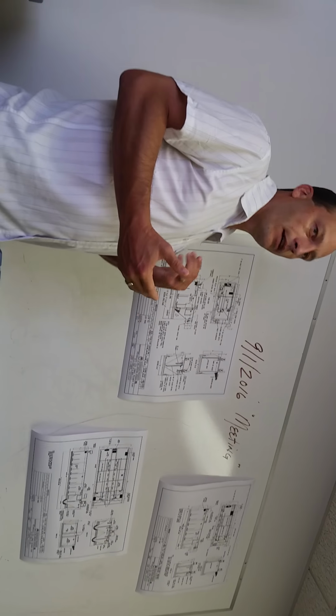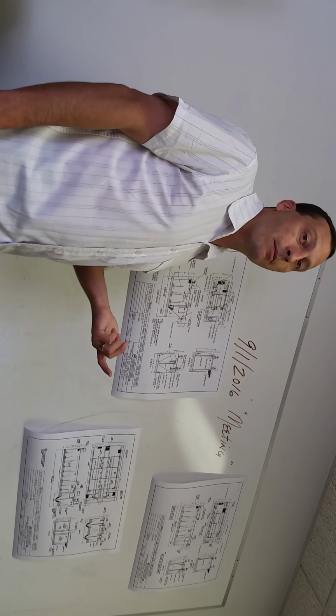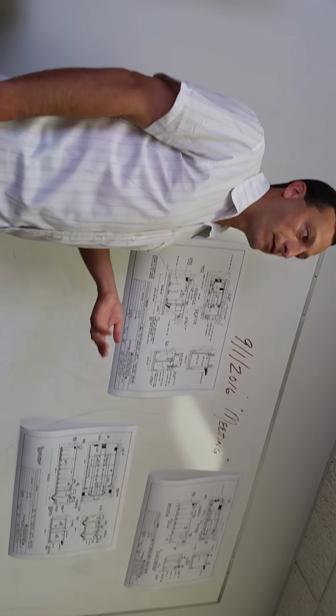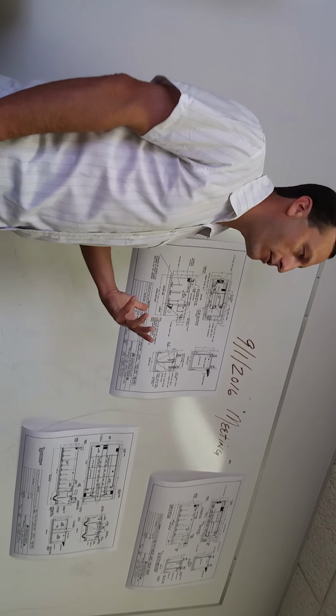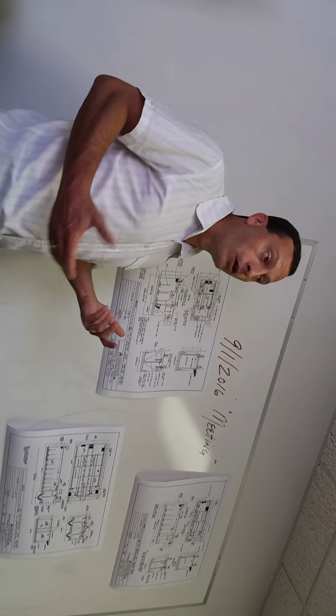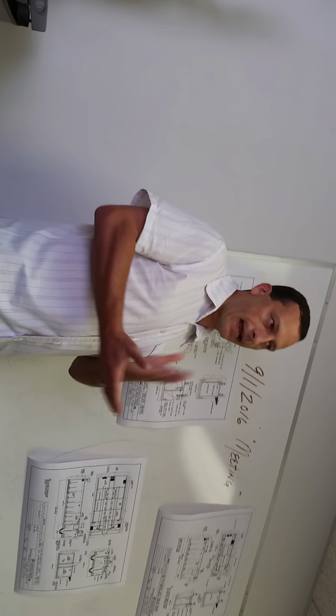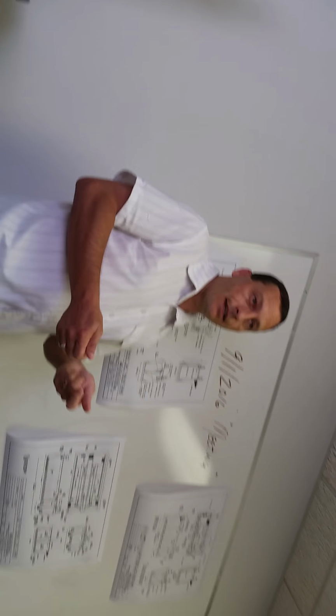And in the EA plant, we still have 2 blowers, but they're going to give each other breaks, and they're only going to run once every 30 minutes, once every hour, once every 45 minutes, depending on what the operator actually sees going on out there. And typically what they should do is run their blower through a cycle, whether it's 15 on, 15 off, 30 on, 30 off. At the end of that 30-minute time period when it's been on, take a DO measurement.